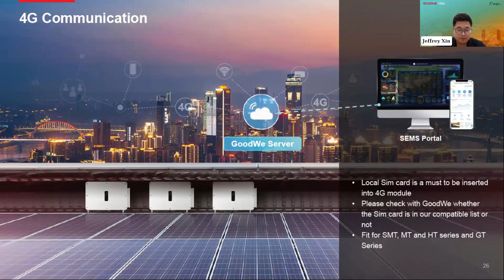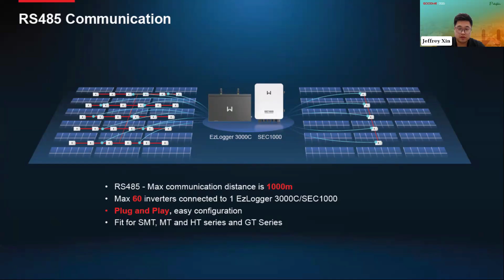Also, between the inverter and the data logger, the general method is RS485 communication. This communication logic is very simple and relatively stable, and also reduces data packet loss. Users can choose to use other brands of data loggers, or we can open the inverter's Modbus protocol content to meet communication requirements. We have also tested compatibility with other brands of loggers used in previous projects.